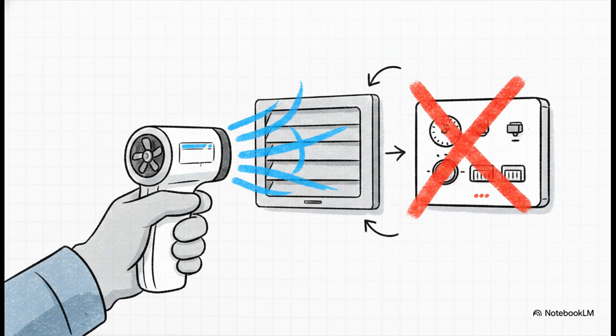You've got to pull out your tools, measure the actual airflow volume, verify the fan performance, and measure that static pressure resistance. Taking actual airflow measurements often reveals the exact physical roadblocks that simple temperature readings just completely miss.